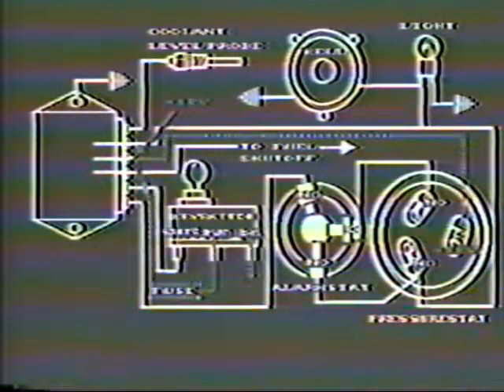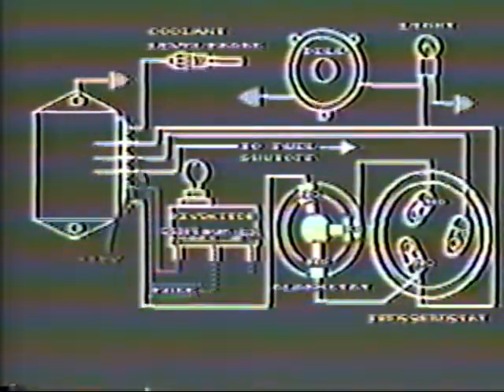When the key is on, terminal 4 has voltage, and so does the pressure stat C terminal, as shown here. The module has an internal switch that can connect terminal 4 to terminal 3. Since terminal 3 has the fuel shutoff wire, when the switch is closed, the fuel will be on and the engine can run. We will call this the run switch. When it comes to starting the engine, we can operate the run switch the same way we did with the 9032 system. Engaging the starter causes voltage to come up on terminal 2. Voltage on terminal 2 causes the run switch to close and turn on the fuel.